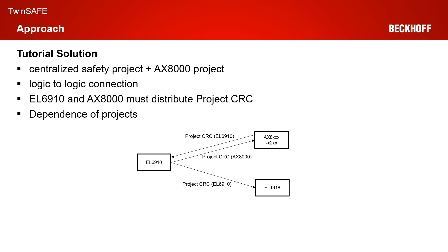If you look at today's tutorial solution, we still have a centralized EL6910 safety project, but the EL6910 is talking to an AX8000, and that AX8000 has its own safety project and its own safety project CRC. So in this case, we have a logic-to-logic connection. For the backup and restore mode, the EL6910 and the AX8000 must distribute their project CRC. We have a dependence of the safety project and we need to configure the backup and restore mode for this dependence, but this can be done very easily within TwinCAT 3.